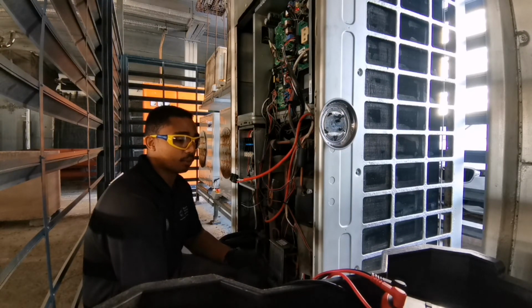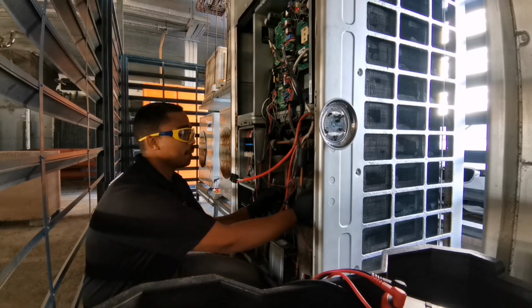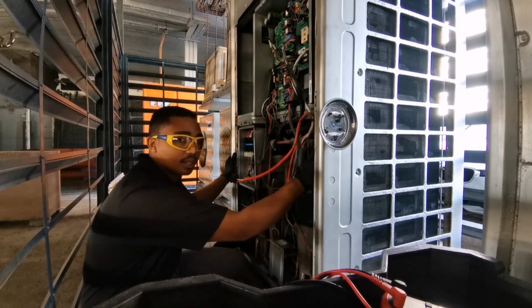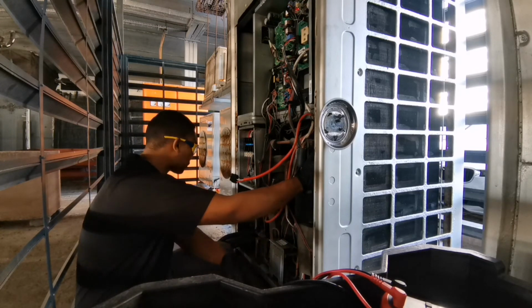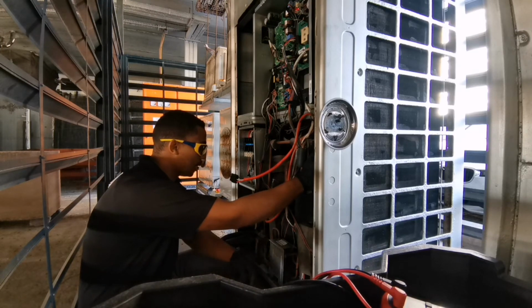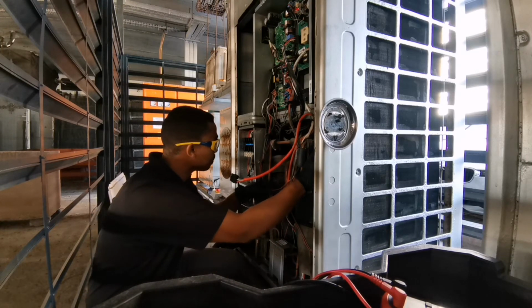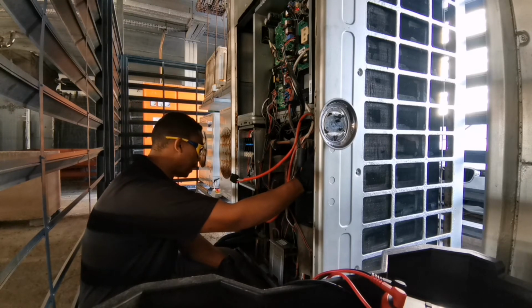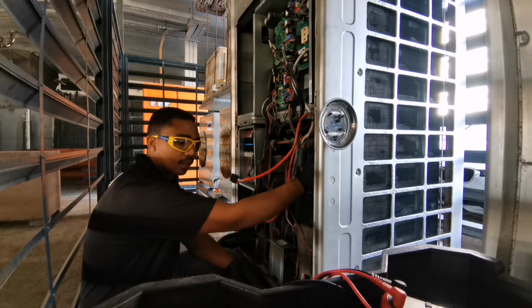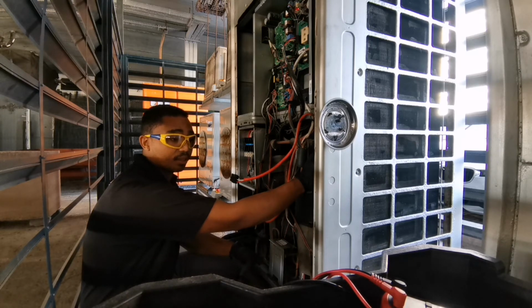Specifically, what I'll say is if you're working on VRF systems, go ahead and replace both compressors inside the system. This condenser, although the other compressor is working, replace them both. So now we've got to find out why our compressor is grounded. It's an oil return issue, causing excessive air temperature, therefore heating up the windings and melting the insulation, shorting out the compressor. Or if it's an oil return valve that is defective. So those are the things that we will have to check.